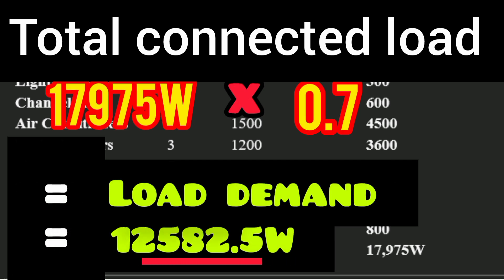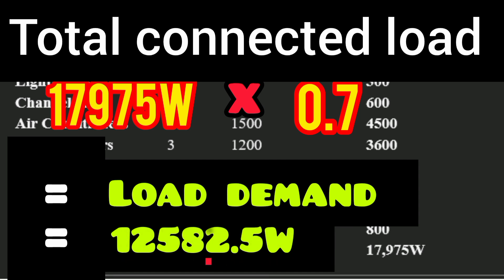This demand load is what we work with — the maximum power used in the installation at any point will not exceed 12,582.5 watts. In the next step we calculate the current, which is our main interest. We have the total demand power and for a single-phase system we have 230 volts.